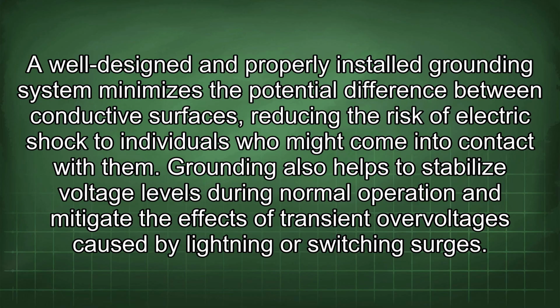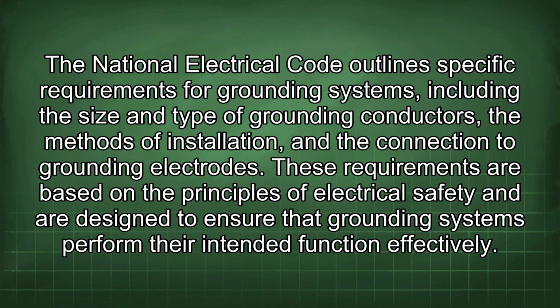Grounding also helps to stabilize voltage levels during normal operation and mitigate the effects of transient overvoltages caused by lightning or switching surges. The National Electrical Code outlines specific requirements for grounding systems, including the size and type of grounding conductors, the methods of installation, and the connection to grounding electrodes.